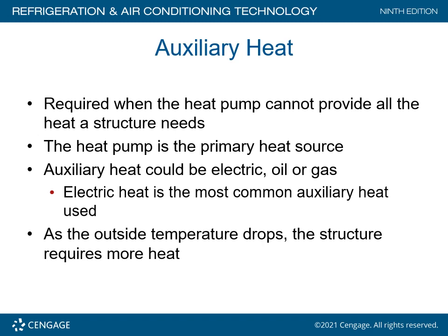Auxiliary heat is required when the heat pump cannot provide the heat the structure needs. The heat pump is the primary source of heating. Auxiliary heat could be electric, oil, or gas. Electric heat is the most common auxiliary heat used. As the outside temperature drops, the structure requires more heat, and this would require the use of auxiliary heat, in this case, probably electric strip heaters.